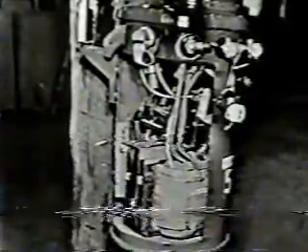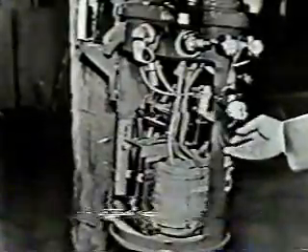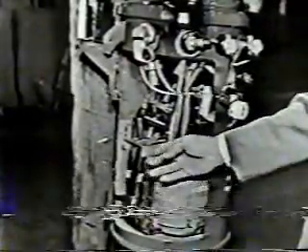Right now, though, we'd like a little bit of an explanation of the very involved insides of this particular transformer here. Well, Bob, this transformer is a cutaway sample. Normally, this transformer is filled with oil on the inside. Here we have all the coils we're going to see being made tonight, the core, as we call it, or the magnetic circuit, all the leads up through to these bushings, which are the high voltage leads connecting to the outside lines, our lightning arrester, which protects the transformer, and the wires coming out to the low voltage, which goes into your home.